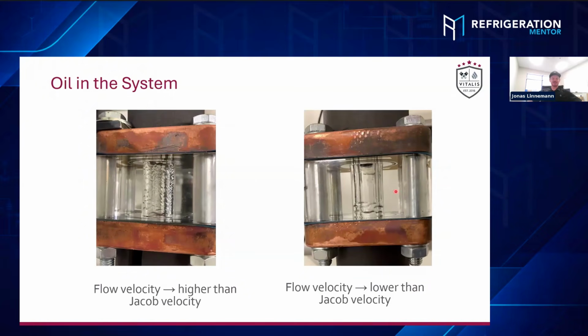Yeah. Like this is basically the same thing. We built a riser in our lab to figure out, okay, that's the theoretical math behind the Jacob's velocity. How does it look in real life? So we basically machined some sections for a riser pipe out of glass and had a VFD driven compressor next to it to just get exactly to that point. And this is how normal oil return looks. You can see at the inside of the pipe, there's this little tiny rope climbing up the line and carrying back the oil. And as soon as you drop below that so-called Jacob velocity, you see that the oil return is right about here to stop. So it's traveling up to here, and then that's it. The layer is ripping apart basically.